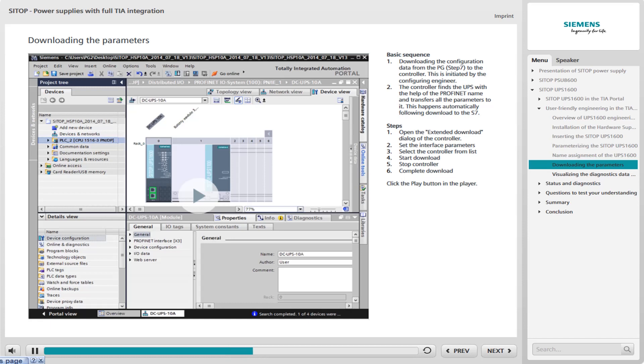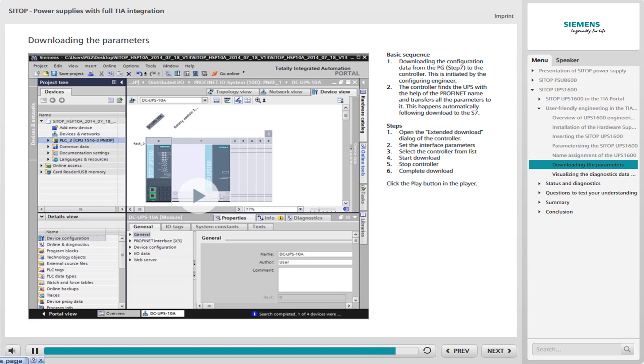Download of the parameters in the TIA portal is completed by the following steps. Initially, you must open the Extended Download dialog of the controller. In this dialog, you set the interface parameters. Then you select the controller from the list. Now start the download. Now stop the controller and complete the download. Click the Play button in the player for a detailed view of downloading the parameters of the UPS 1600 in the TIA portal. You can pause the simulation and jump backwards and forwards.